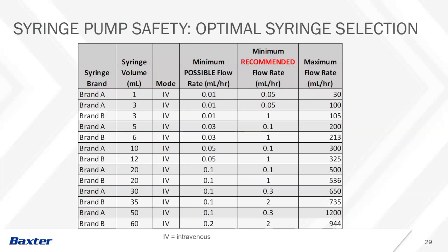Additionally, syringe size matters. Knowing the minimum recommended flow rate for each syringe size is essential. Generally, the smallest size compatible syringe should be used. This is of particular importance with high-risk, life-sustaining medications running at low infusion rates. Think less than 1 milliliter per hour.